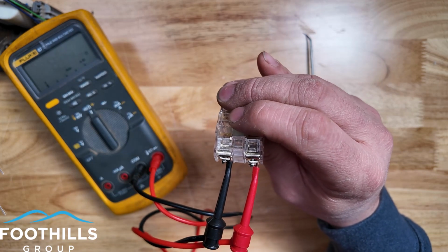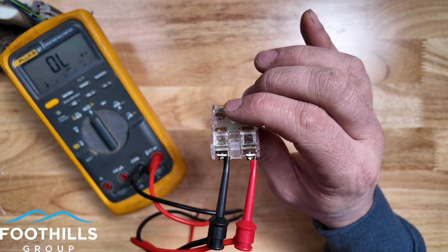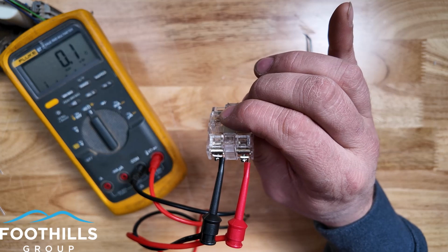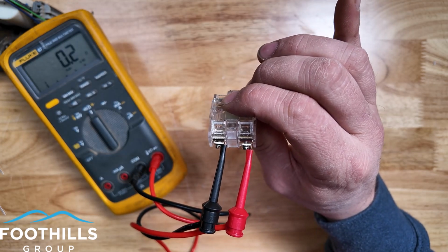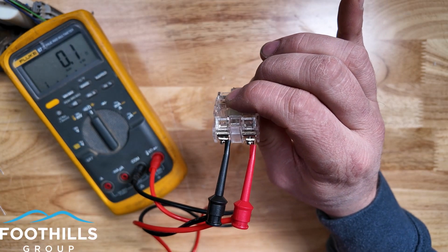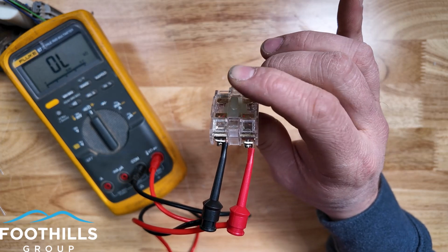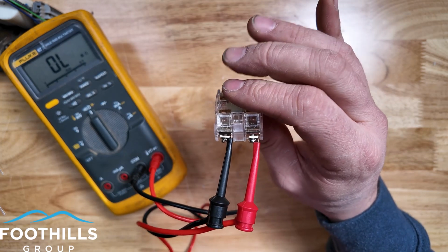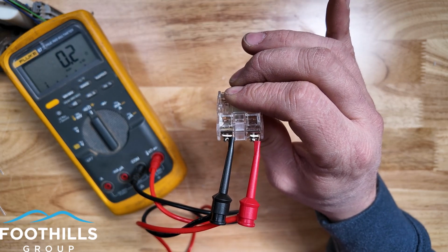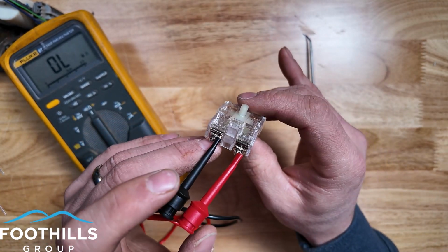And that is ultimately what we're looking to test. When you're working with a switch that's not working properly, sometimes you feel like you have to push it a few times before it finally works. What you're doing is rubbing through the arcing or the oxidization on those contacts to finally get them to work. And you can see that as I bump it around now, I'm down to 0.1 ohms, which is what I'd expect to see. And so that means when we release it, we are open, OL. When we close the contacts, we are down to 0.3, which is a closed switch. So this is a normally open momentary switch.